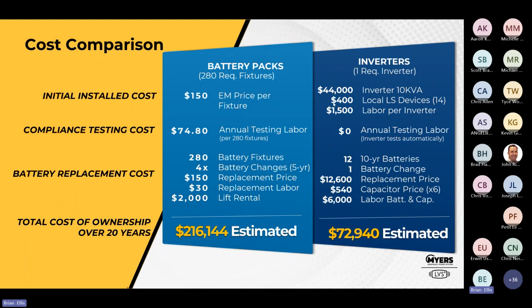Looking at this from the inverter, we have one 10 kVA inverter. We have 14 of these load shed devices. We got a little bit of labor to install the inverter, no doubt. And then these are 10-year batteries. So we'll probably get more than 10 years out of them. But let's say we have to replace the batteries after 10 years. We're still looking at $70,000. Ease of testing and maintenance. It's really a no-brainer in comparison to battery packs.